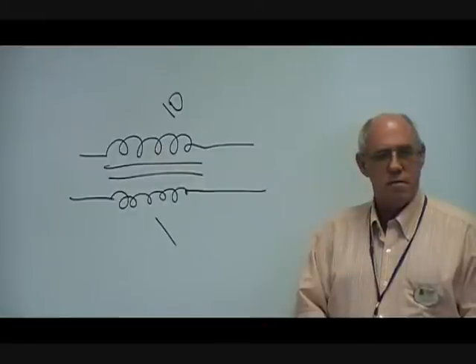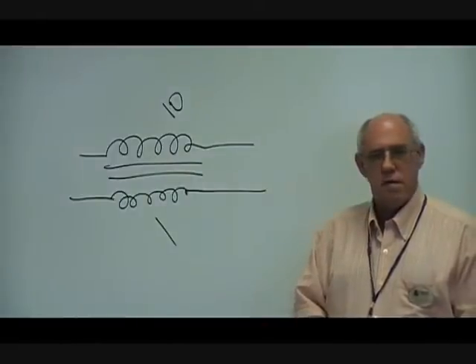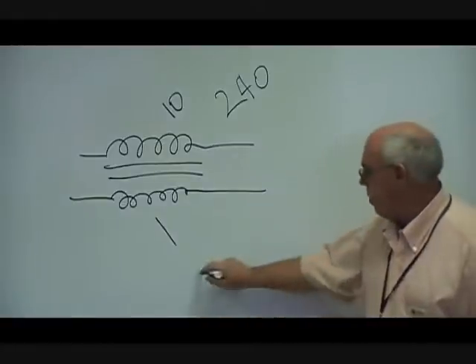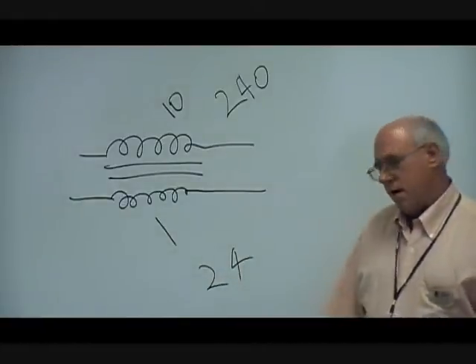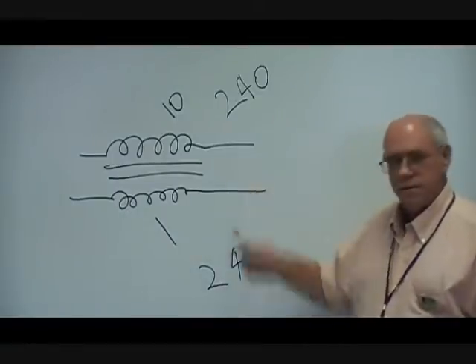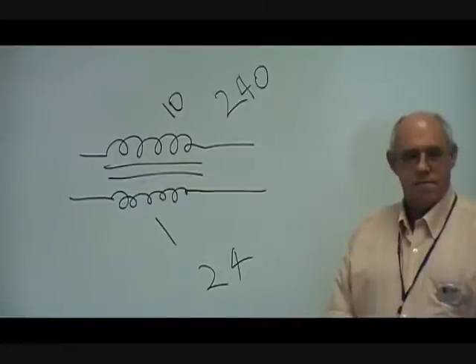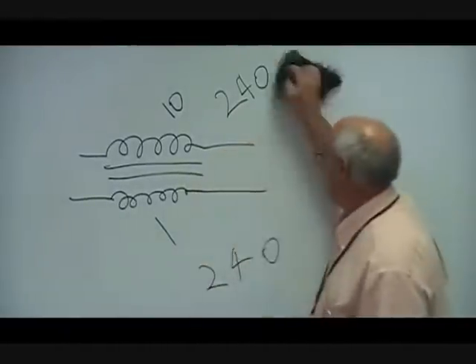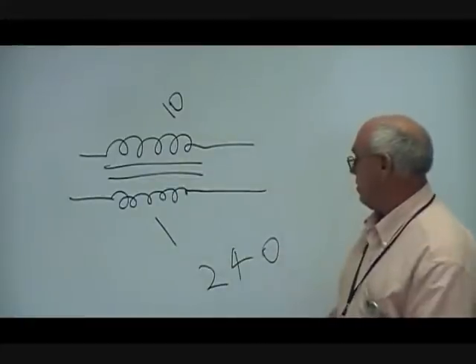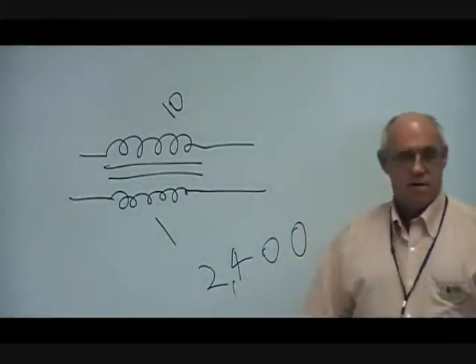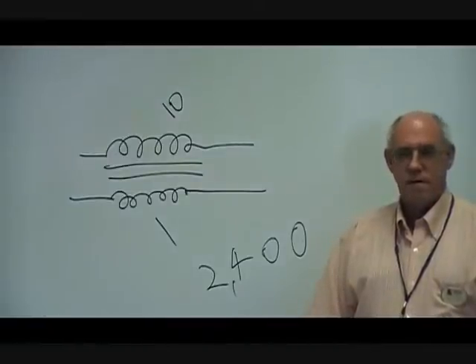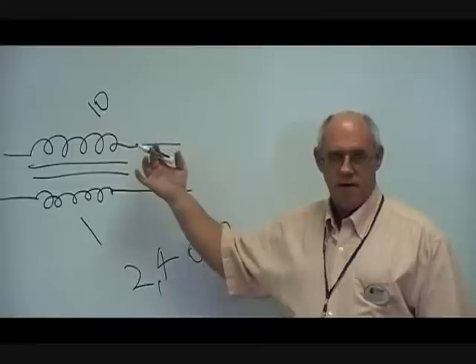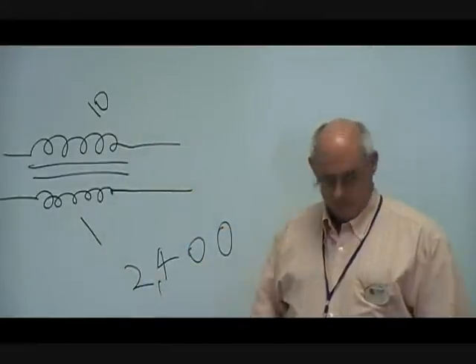Can you think of where you'd see that? For example, if the primary is 240 volts on a step-down transformer, the output would be 24 volts. But what if you hook it up backwards — put 240 volts on the secondary side? You'd get 2,400 volts out. The insulation is not going to stand up; it's going to burn the transformer. And if you happen to have your hands on that when it's hooked up wrong, you're going to get hurt.